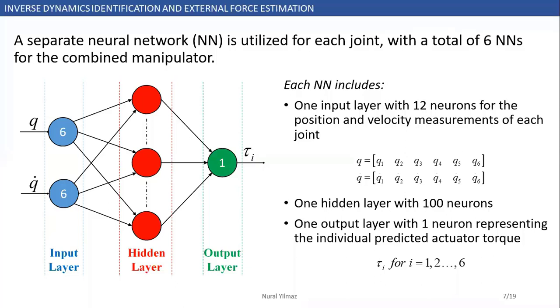As I already said, a separate neural network is utilized for each joint. In total, we make use of six neural networks for the DaVinci Research Kit. If we look at the network structure, each model has one input layer with 12 input neurons, which are position and velocity measurement vectors. There is one hidden layer with 100 neurons. Also, we have one output layer with one neuron representing the individual predicted actuator torque.